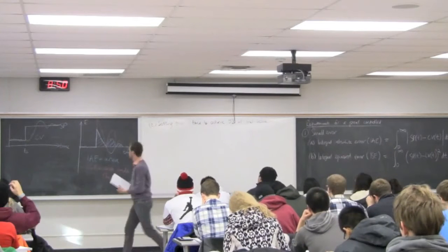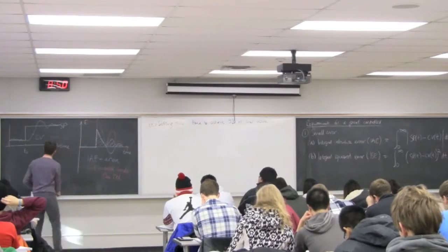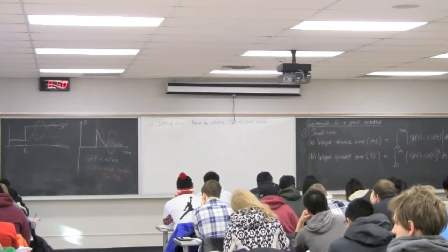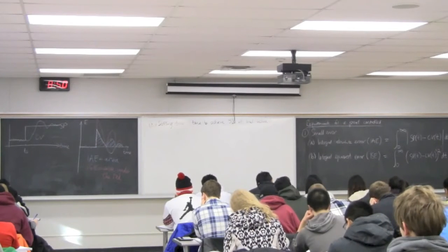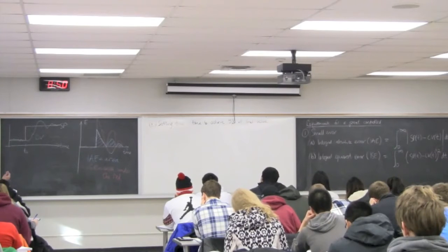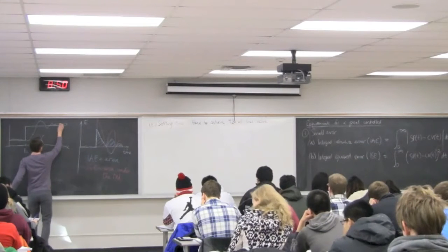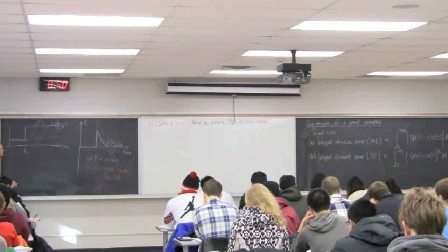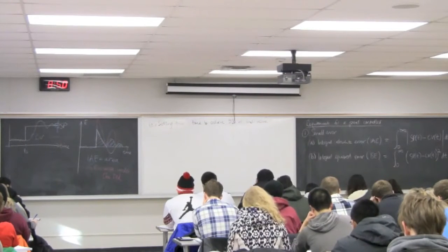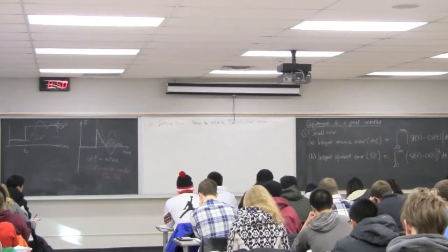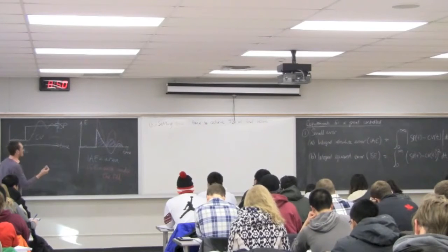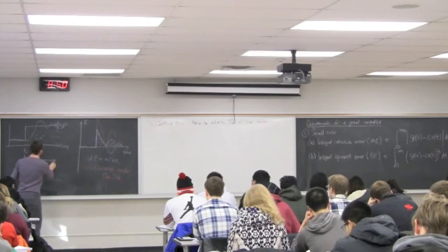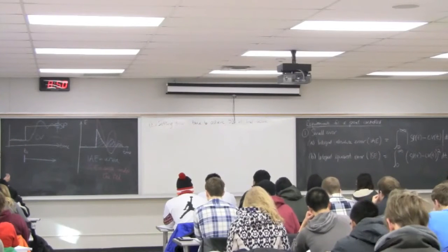In the context of this curve over here, this diagram, the green curve is my control variable. Once it's within about 5% of the desired final value, so somewhere around here, you can calculate a 5% limit. The moment that green curve enters into that zone, it's about 5%. What we're saying, this is the time taken. So the time from when we make the set point change to when we achieve that settling time.